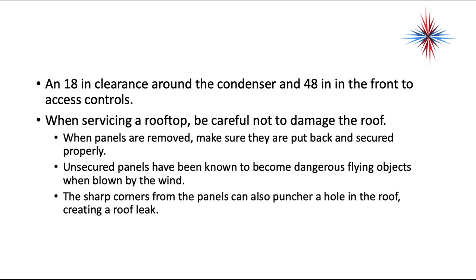When servicing a rooftop, be careful not to damage the roof. When panels are removed, make sure they're put back and secured properly. Unsecured panels have been known to become dangerous flying objects when blown by the wind. The sharp corners from the panels can also puncture a hole in the roof, creating a roof leak.